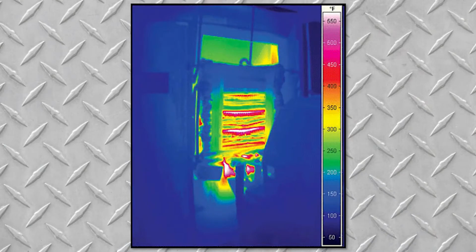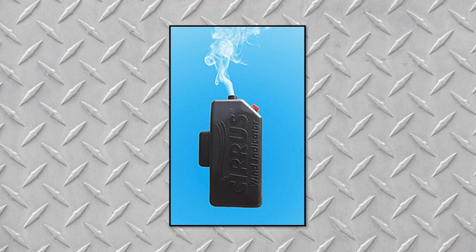Sometimes more important than insulation is looking for where air or combustion products may be leaking through cracks, fittings, gaps, or openings where products come in and out. Those furnace openings can be minimized or closed when not needed. Again, you can use your infrared camera to look at these hot spots as shown in this figure.